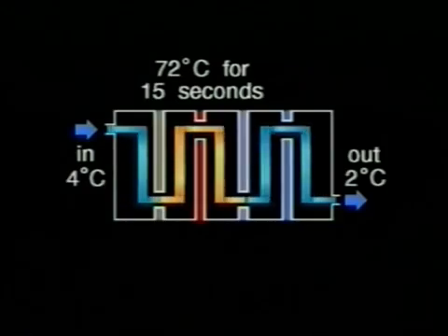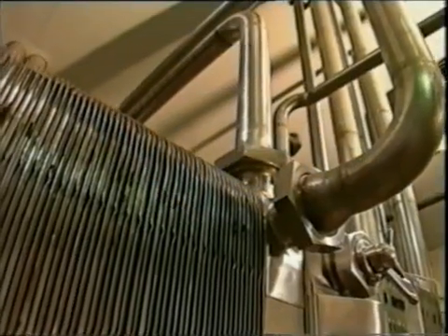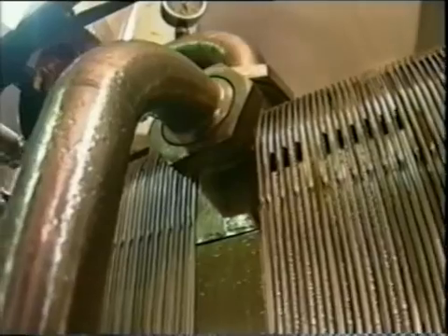This process is known as HTST, which stands for High Temperature Short Time Pasteurisation. It's a continuous flow system designed to kill bacteria quickly and minimise the damage to the flavour and food value of the milk. The pasteuriser consists entirely of plate heat exchangers. The milk never comes into contact with steam or cooling water.